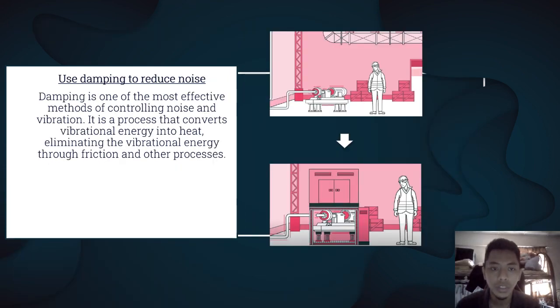Lastly, use damping to reduce noise. Damping is one of the most effective methods of controlling noise and vibration. It is a process that converts vibration energy into heat, eliminating the vibrational energy through friction and other processes. As we see in the picture, in the first picture we can see that the motor is vibrating, and in the second picture we can see the use of a damper lessen the noise.